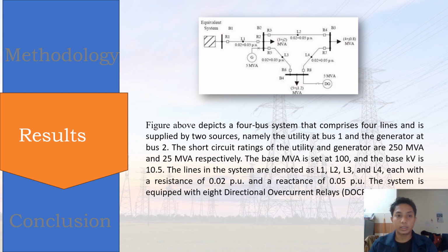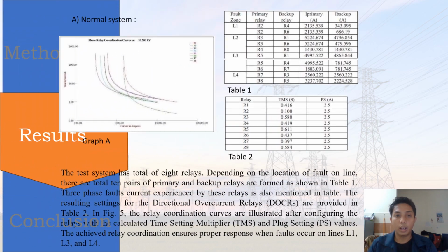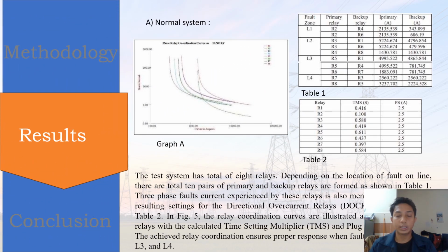Okay, here there are 3 types. First is the normal system, second is line loss, and that is going to be explained by my friend. Okay, for the normal system, here is the graph and table for the normal system. The test system has a total of 8 relays. Depending on the location of the fault on the line, there are a total of 10 pairs of primary and backup relays formed, as shown in table 1.